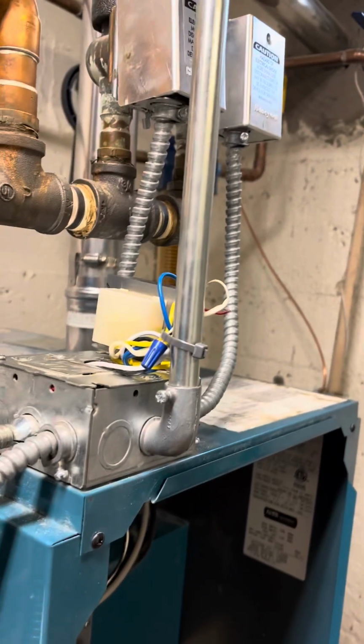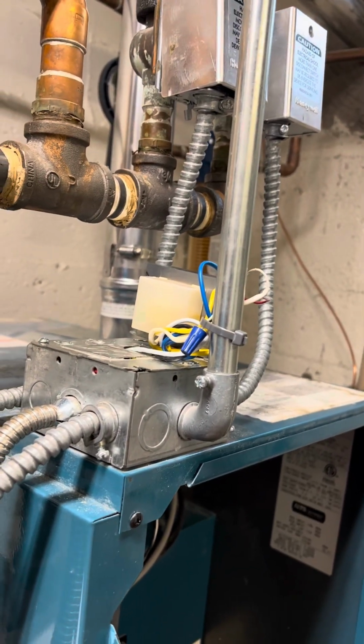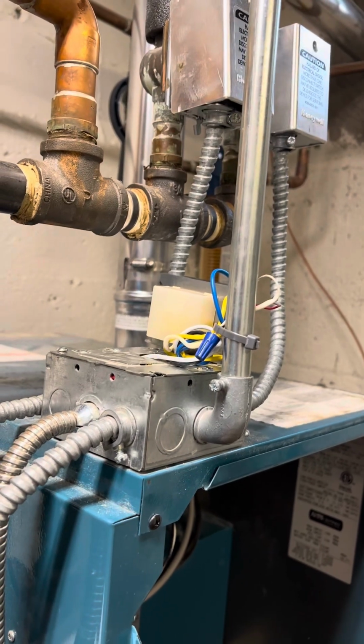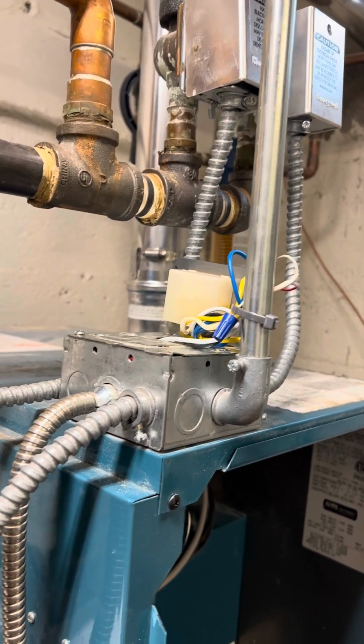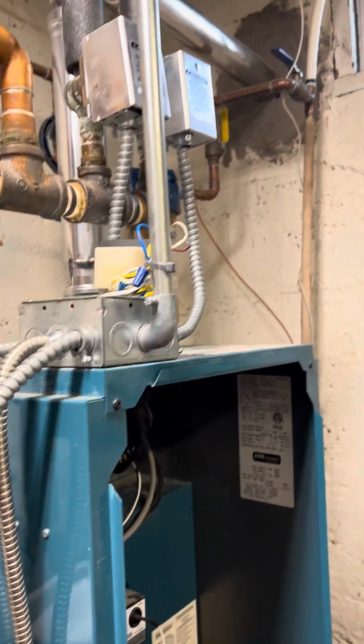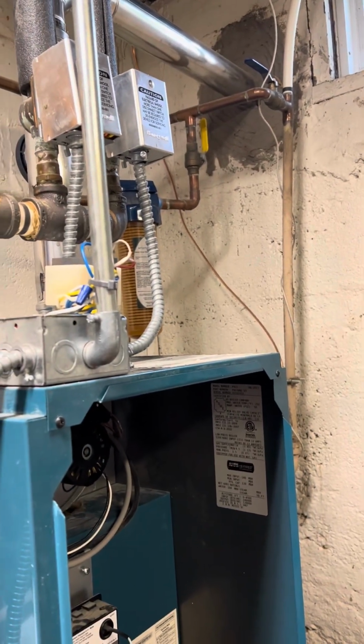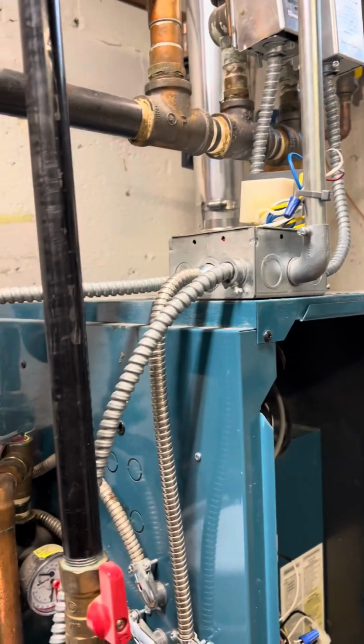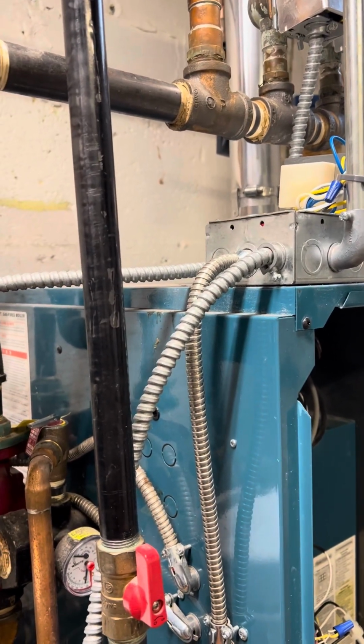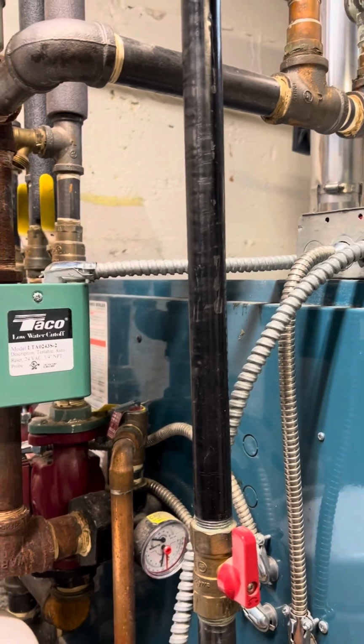So we had to change the transformer, and then we had to keep the amp meter on there and figure out which one was the bad motor or bad wire or something grounded. So we found out that the zone valve was no good, so we changed out the zone valve, and we get a call back again today saying that there's no hot water.